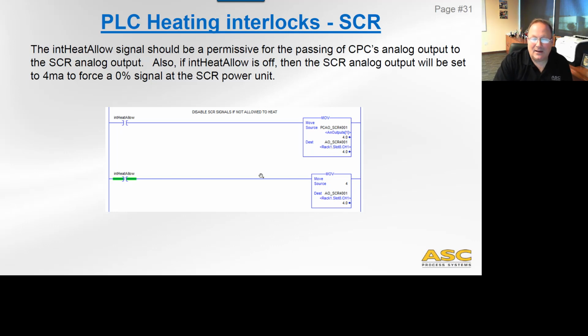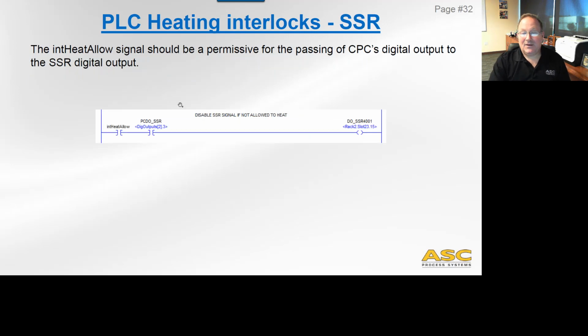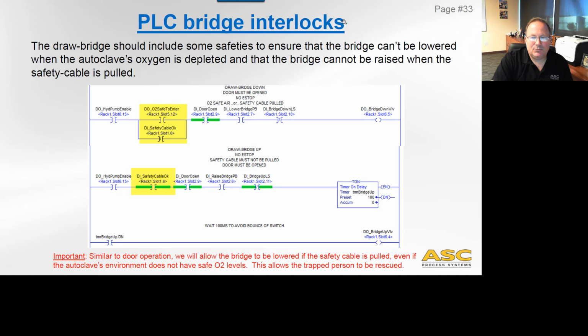If it's not heat allow, then we're going to move a 4 there. So just blocking this alone does not change this AO. You actually have to have another rung here which forces the 4 to the AO, and 4 being 4 milliamps and 0%. And if we have SSRs on the autoclaves, smaller autoclaves, then it would work this way. Okay, you would have heat allow in the rung as a permissive to the PCDO, digital output. Whoops. So now we have PLC bridge interlocks.